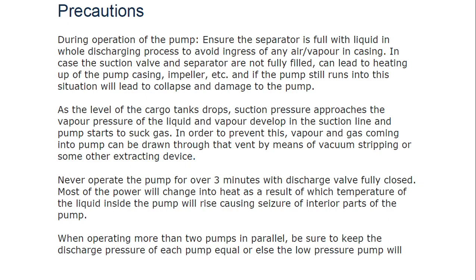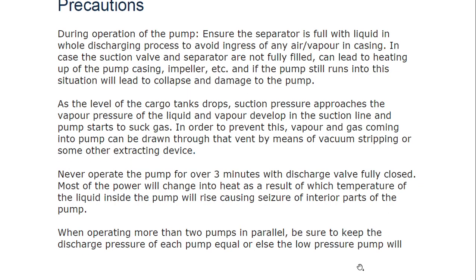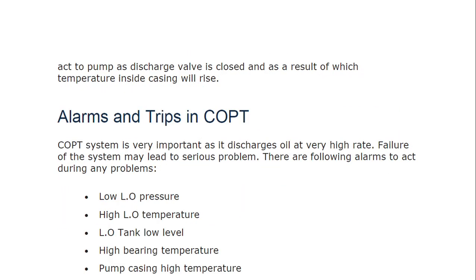When operating two pumps in parallel, be sure to keep the discharge pressure of each pump equal. Otherwise the low pressure pump will act as a resistance — with its discharge valve effectively closed — and as a result the temperature inside the casing will rise.